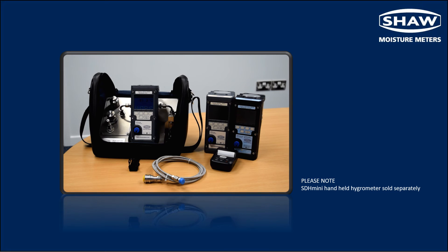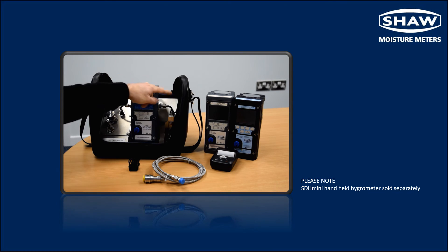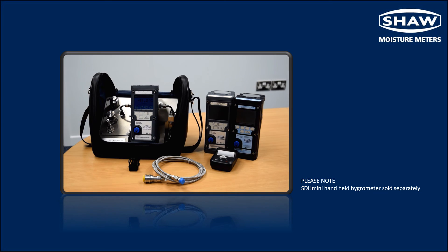A sample flow rate of two to five litres per minute is ideal for the Shaw sensor. The sample gas exits the flow meter and can be vented to atmosphere or returned to the process line.